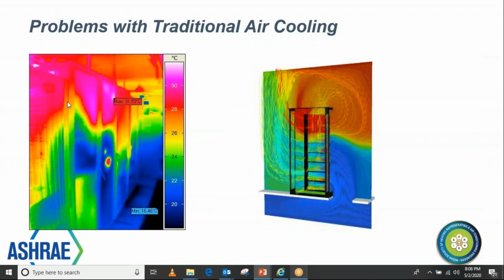Then suppose you are not able to meet the required flow rate, what happens? You can see here, on the left side is a picture of a data center, a thermal picture. On the right side, you can see a CFD picture where cold air is entering from the raised floor into the rack, and then through the rack, after exchanging the heat, it is coming out. But what is happening is only in the lower portion the cold air is sufficient, but it's not reaching up to the top. Why? Maybe because sufficient air is not coming out, or because there is a lot of loss of cold air from the bottom portion. In either case, hot spots come up on the top.